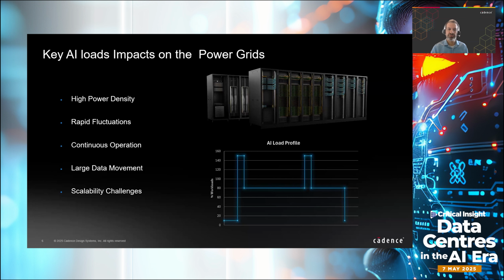It's also the profile of power within AI compute. We see rapid fluctuations from idle power to way over the design load, 50% in some cases over its thermal design load, in millisecond spikes that could take a rack from a few kilowatts up to 600 kilowatts, or currently 120 kilowatts for a full rack. So how you deal with that from a provisioning perspective is very challenging.